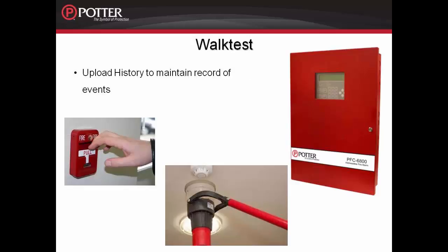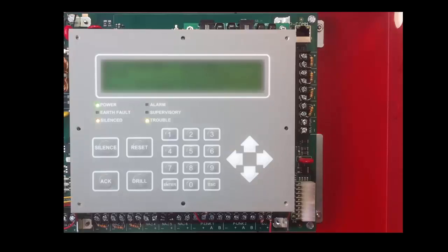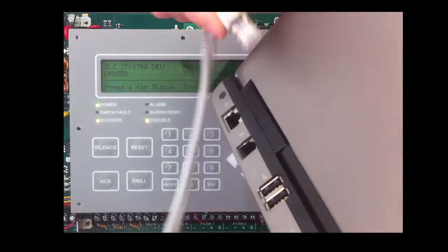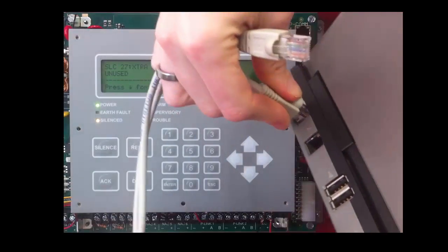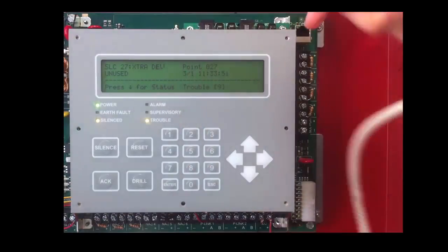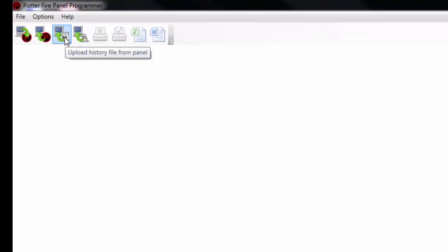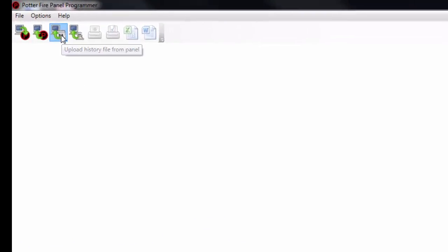Prior to starting walk test, when you arrive at the site, upload the history to maintain a record of events since the last site visit. Connect the laptop computer to the fire alarm control panel and launch the programming software. In the programming software, upload a history by clicking on this icon that you see here.